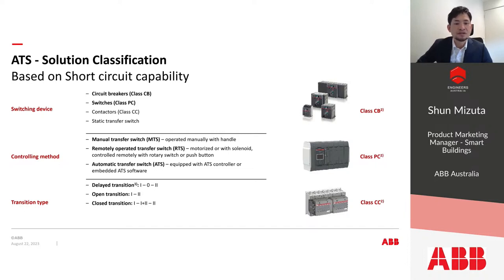We have three different transition types. Delayed transition: in this case, there is a stable off position in between the transition. Second one is open transition, so the transition will happen directly from primary source to secondary source. Third one is closed transition, where you can see there is an overlapping period between transition. In the IEC region, delayed transition is more preferred, making up 99% of the market. On the other hand, in the UL region, open transition covers 80% to 90% of the market.